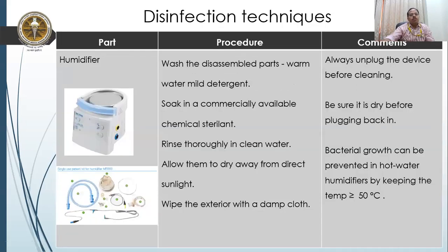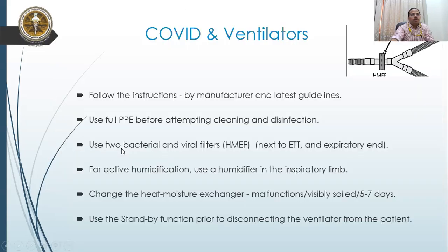The same procedure is to be used for the humidifier, as it is shown in this picture. Just remember that these are electronic devices. So always unplug the device before cleaning and make sure that there is no water content while you add or reattach this equipment.